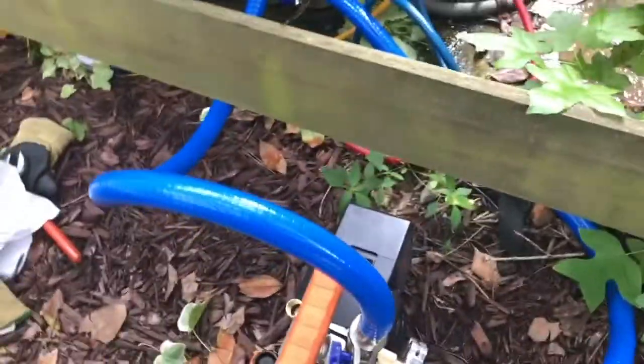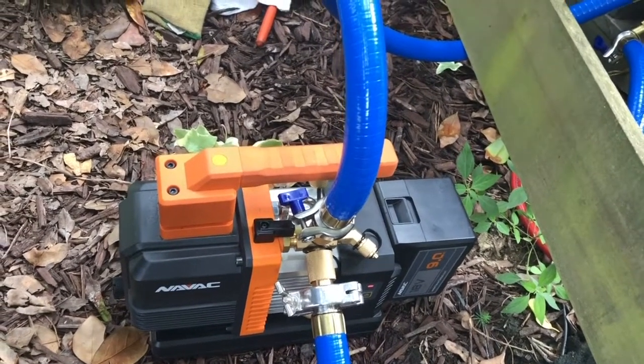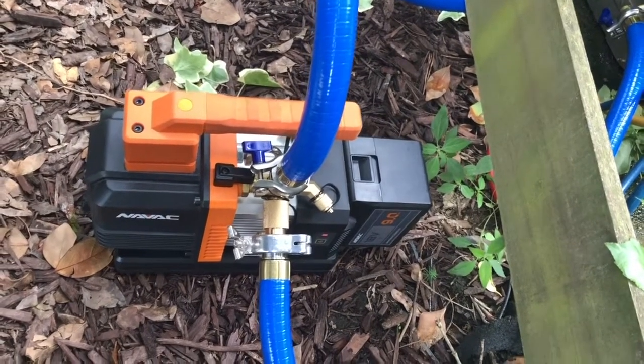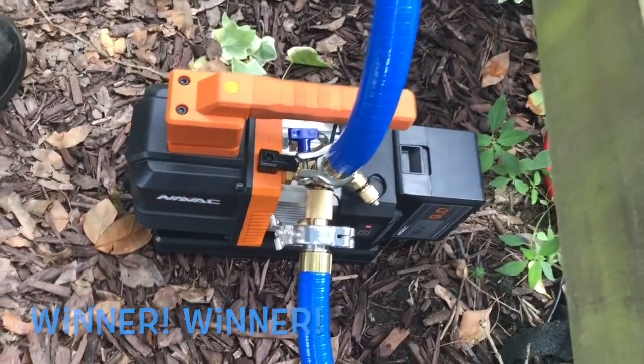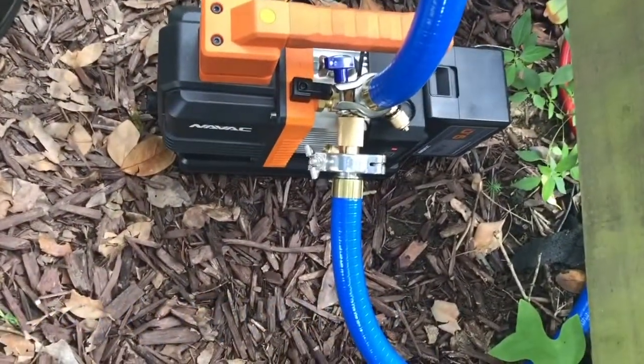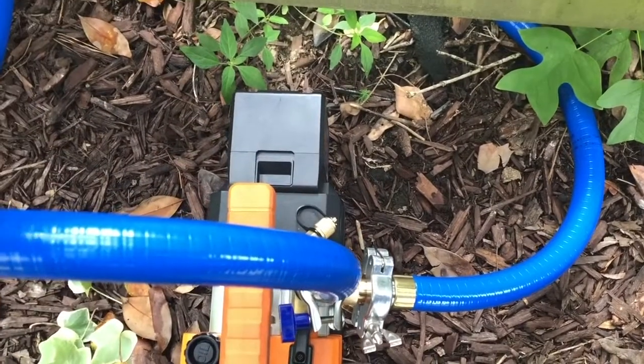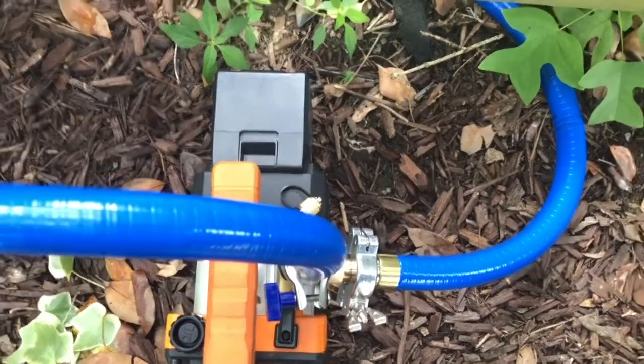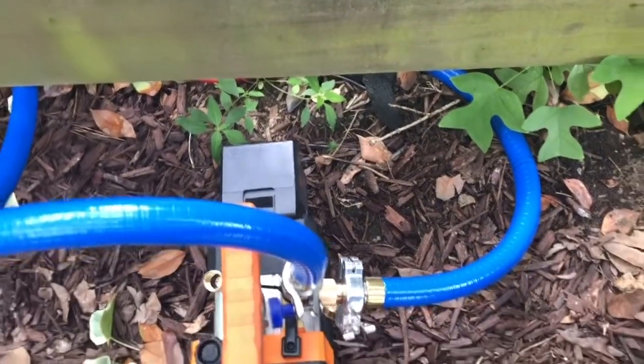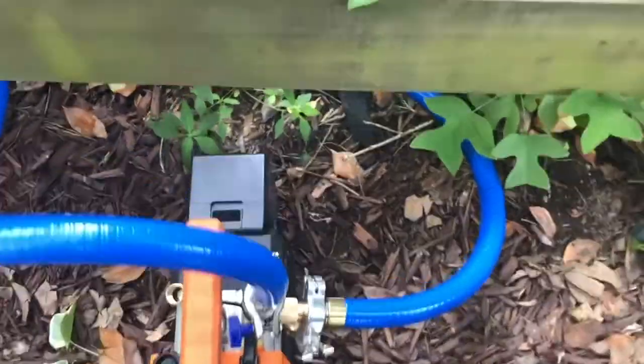Back to the pump — this is my true review. I've used this pump for a few months now on several applications. To me it's a game changer. You can lift this thing up, take it on a roof if you had to, it's so small and compact. Now regarding the battery: I've had two different instances — one battery lasted 45 minutes, the other only about 38 minutes — so if you're going to be pulling for a while, it's important to have two batteries.